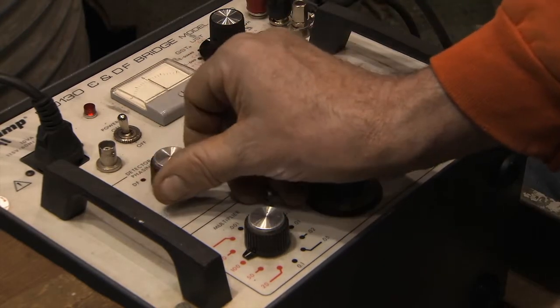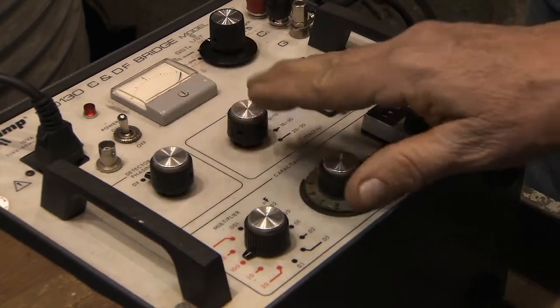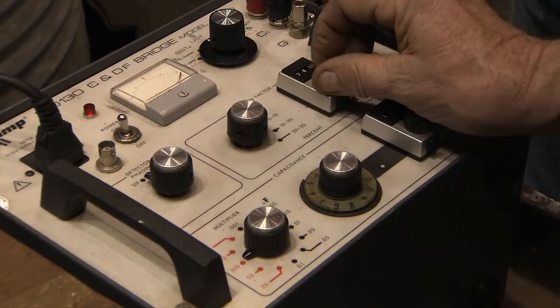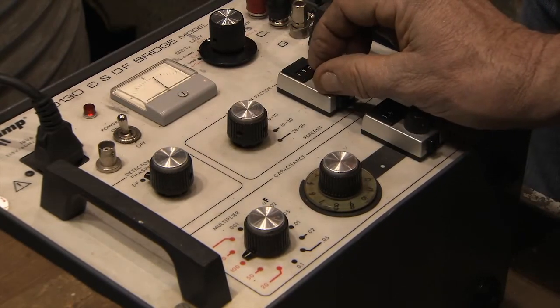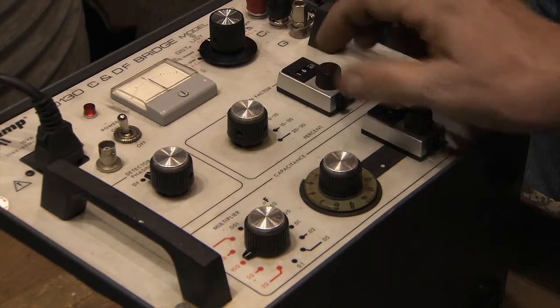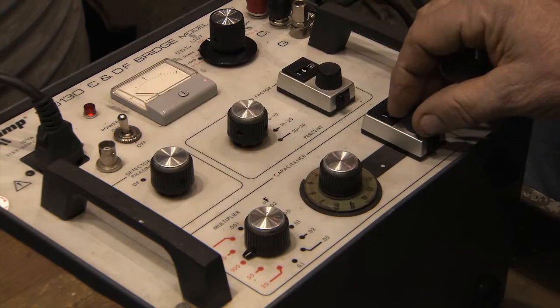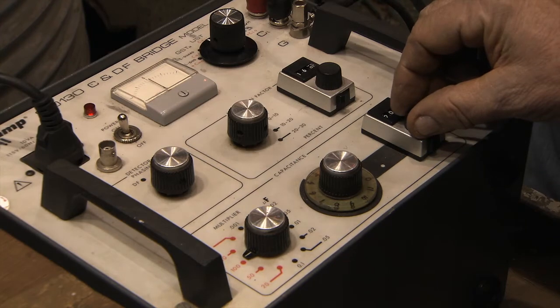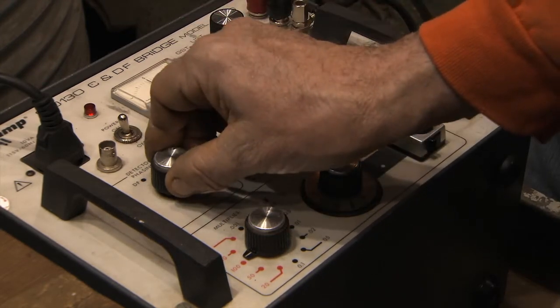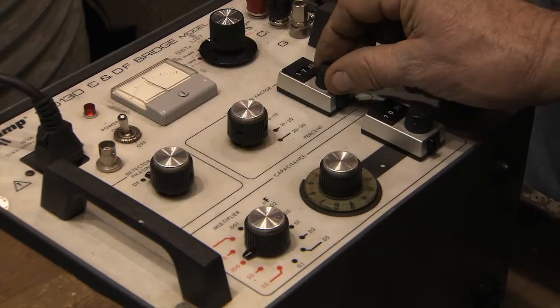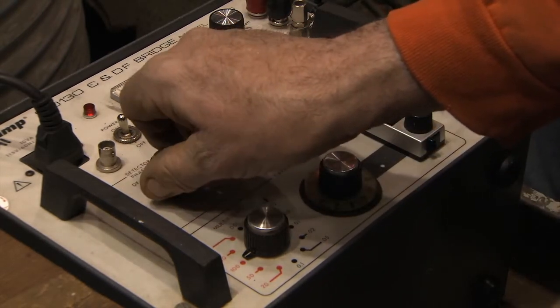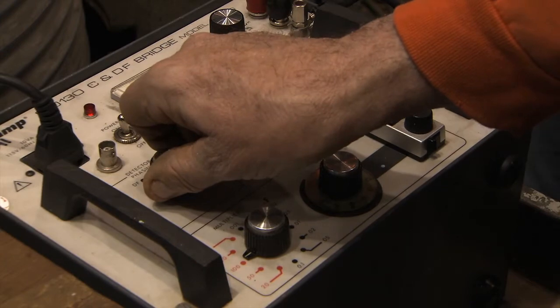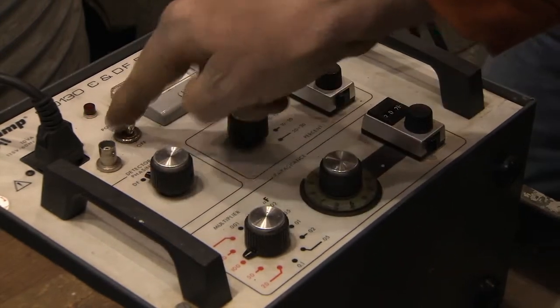Then we go to the dissipation factor and it's showing that it's very high right there. So we're going to try bringing it down and bring that to 0. We go back and forth because they affect each other. Now we're going to bring this up to 0. We go back to dissipation. And we finally reach a point where they both stay at 0. And that's your reading then.